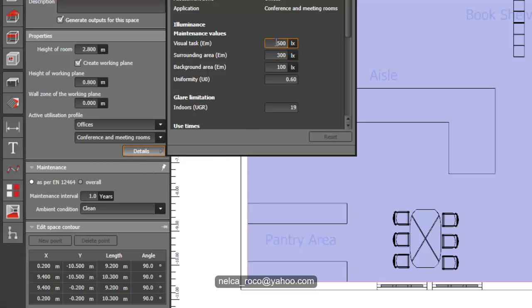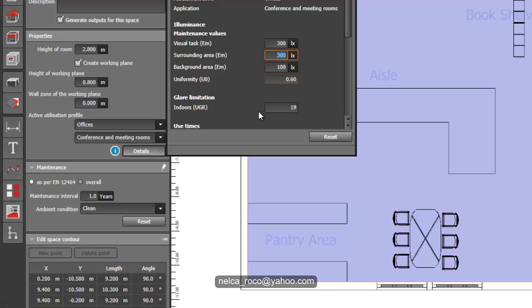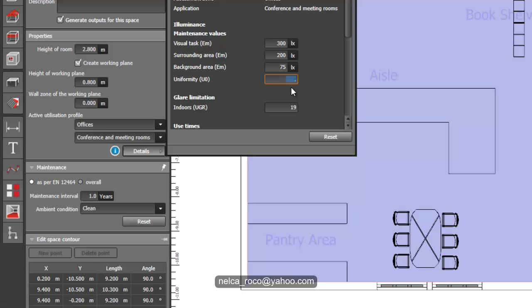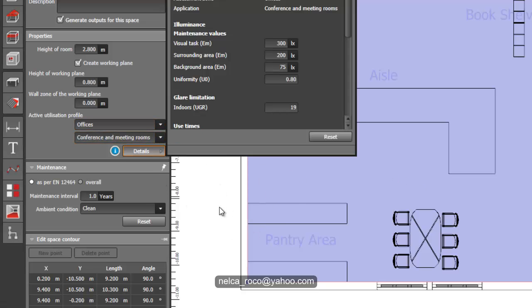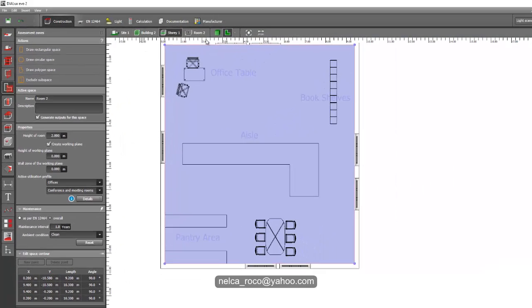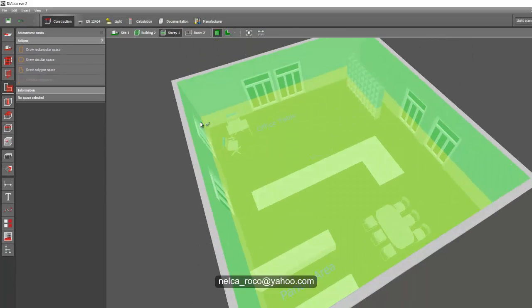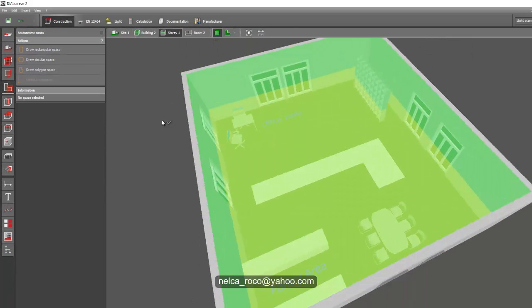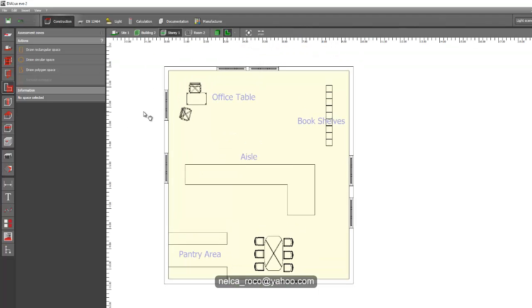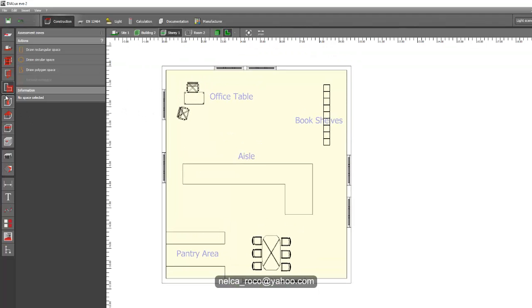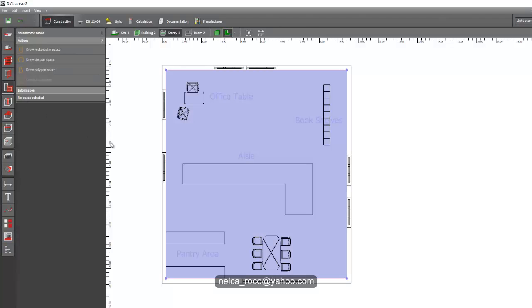Click the details tab and you will see that 500 lux is the default, as you observed. But of course you can change it. If you want to change it into 300, then you may change it into 300. The surrounding areas become 200 and the background maybe 75. You can also change the uniformity here. If it's 0.6 and you want to make it 0.8, then you can do it.